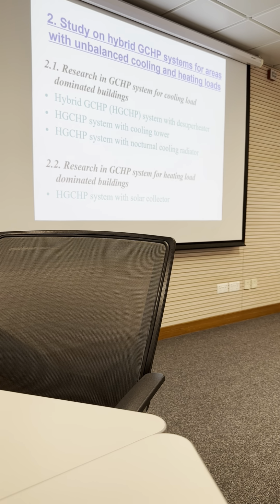First, we did some research for cooling load dominant buildings. We developed the hybrid ground coupled heat pump system with a desuperheater, with a cooling tower, and with a nocturnal cooling radiator, by three means. Then let's see how to do it. We also did some research on ground coupled heat pump systems for heating load dominant buildings like Harbin. Nearly no cooling is necessary in summer, only heating.